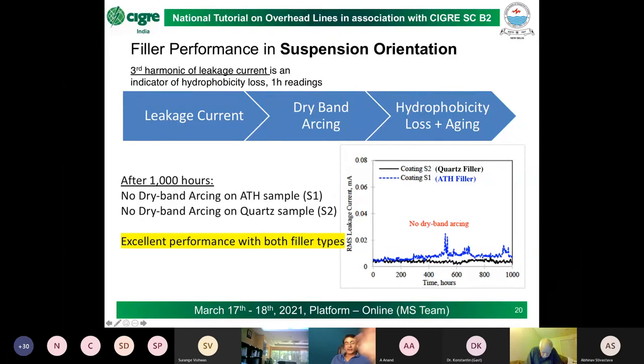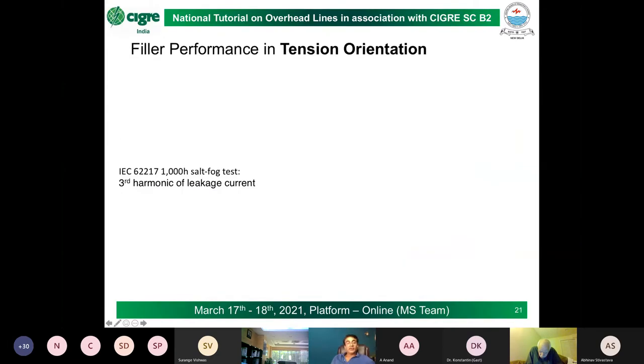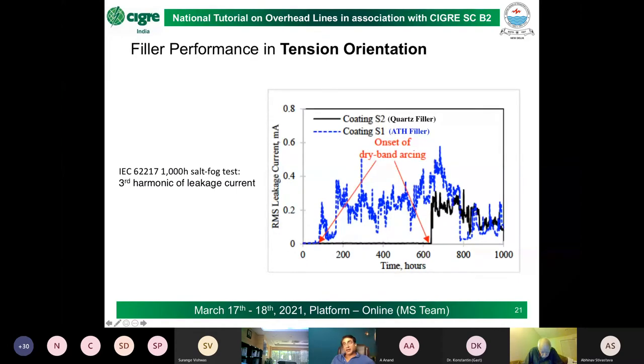So all kinds of coating, quartz fillers, ATH fillers, in the suspension vertical orientation, there has been almost no difference in performance. Everything works really beautifully, all is well. But suddenly when you take this same insulator and put it into tension orientation in this 1,000-hour salt fog chamber, what you see is this quartz filler, what we see in S2 here. If you look at the bottom of the graph, the black line, this is near dead till well past 600 hours, about 640 hours, there is no leakage current.